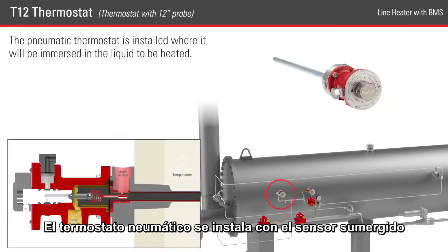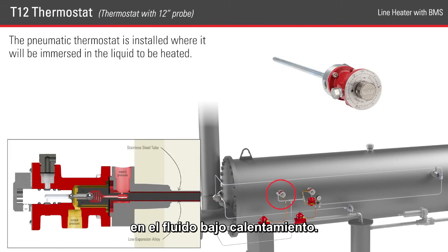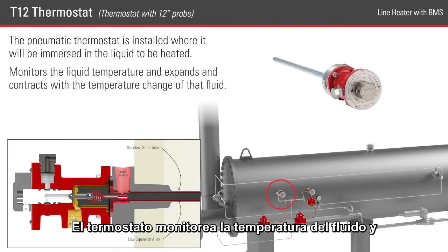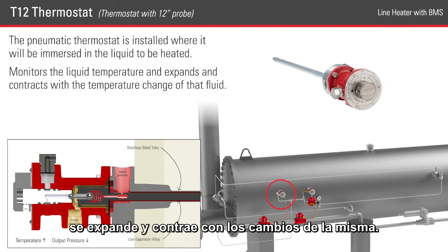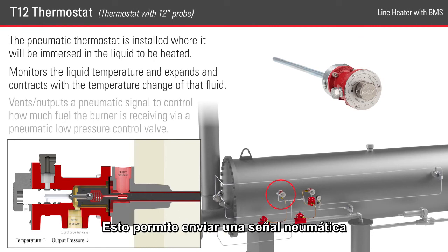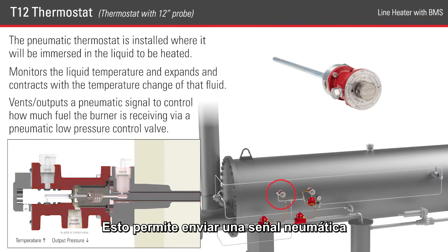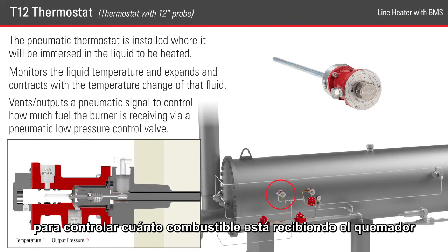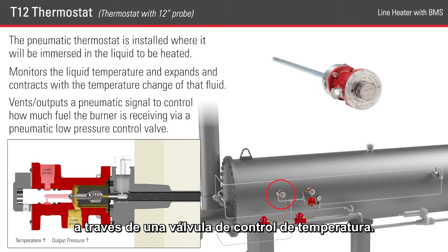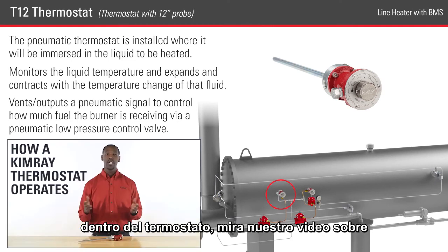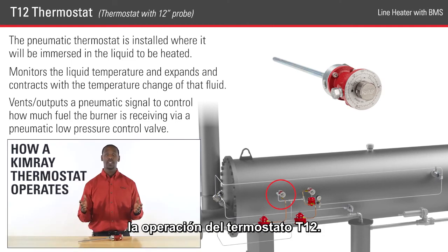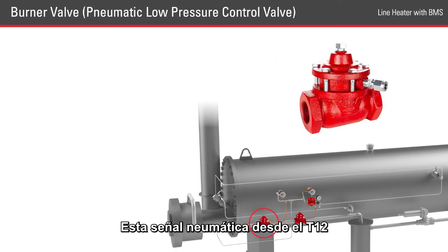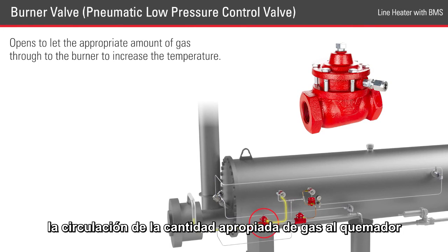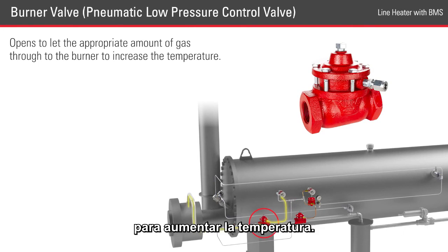The pneumatic thermostat is installed where it will be immersed in the liquid to be heated. The thermostat monitors the liquid temperature and expands and contracts with the temperature change of that fluid. This positions the pilot plug to either vent or output a pneumatic signal to control how much fuel the burner is receiving via a pneumatic low-pressure control valve. For a more technical explanation of what is happening inside the thermostat, watch our video about the operation of the T12 thermostat. This pneumatic signal from the T12 is sent to the burner valve. The burner valve opens and lets the appropriate amount of gas through to the burner to increase the temperature.